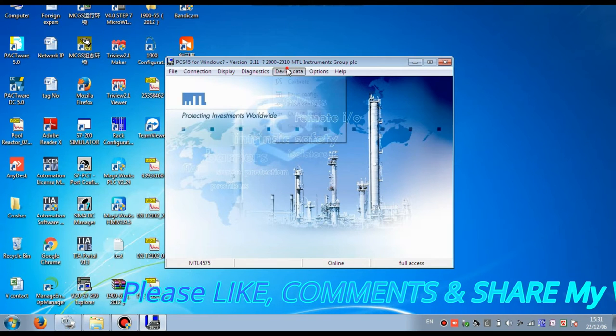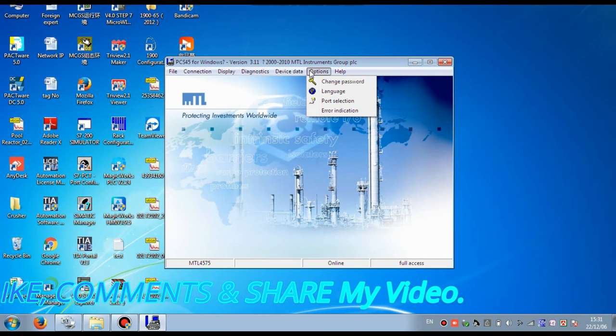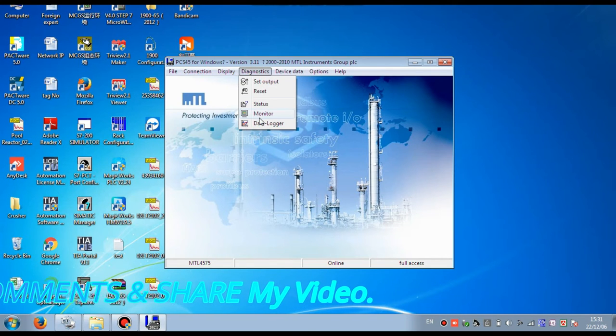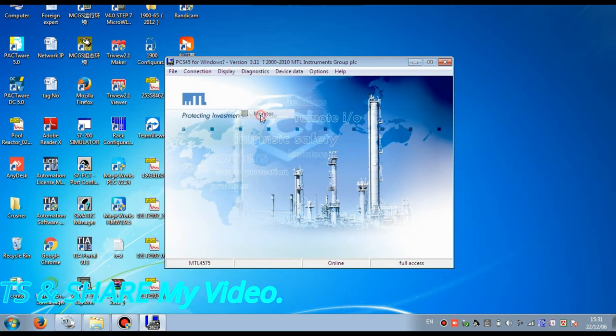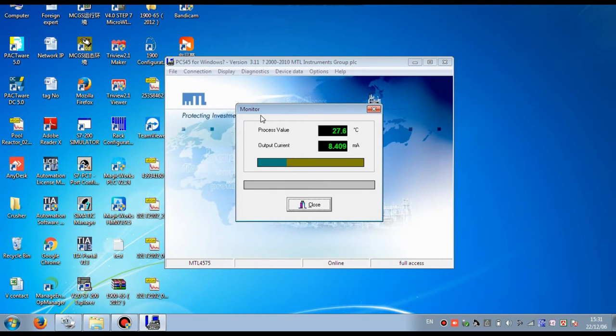After configuration is finished, you can also set the password and language selection for different parameters. Now go to Diagnostic and press Monitor. Here we can monitor the live value that we already configured. The process value is showing 27.6 degrees Celsius and the current output is 8.41 milliamps — that means our MTL is configured correctly.